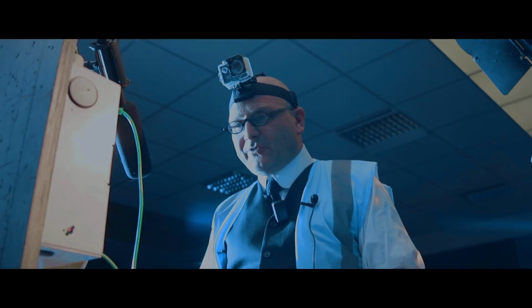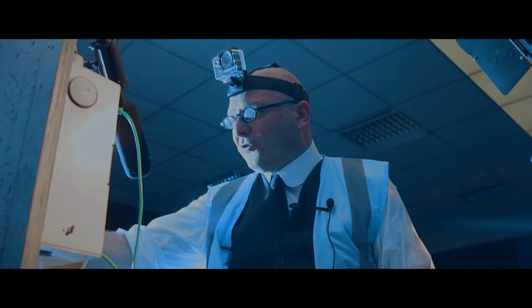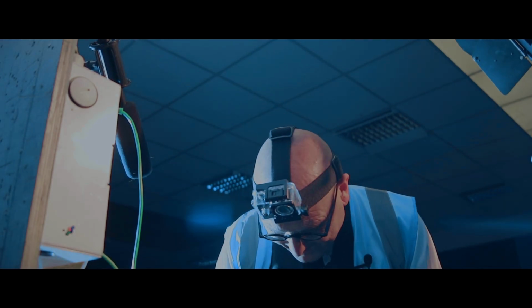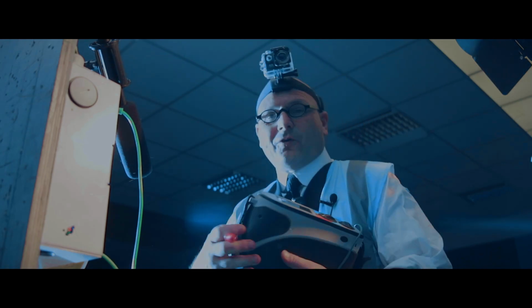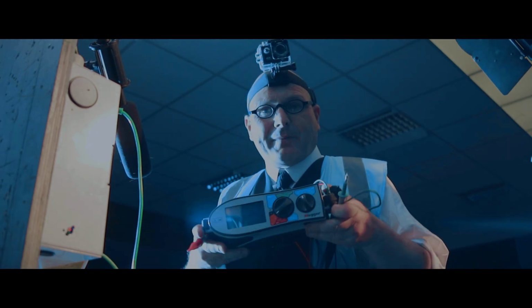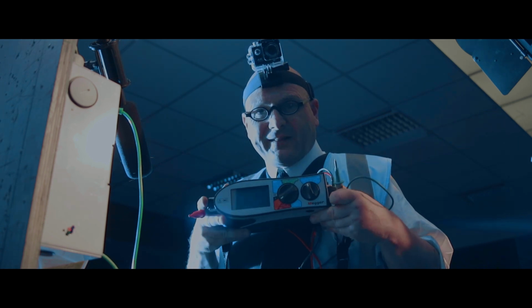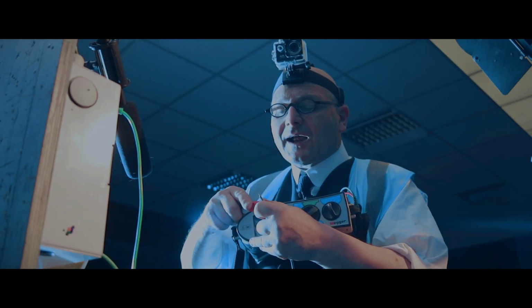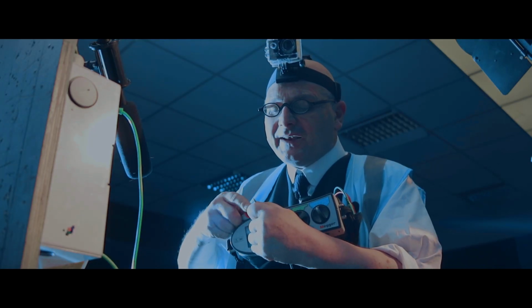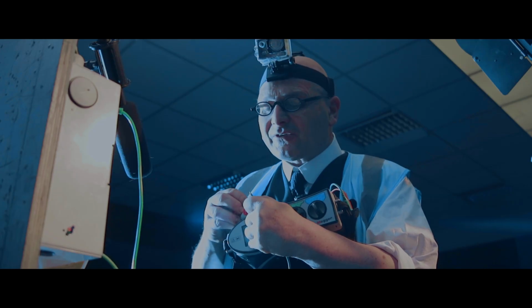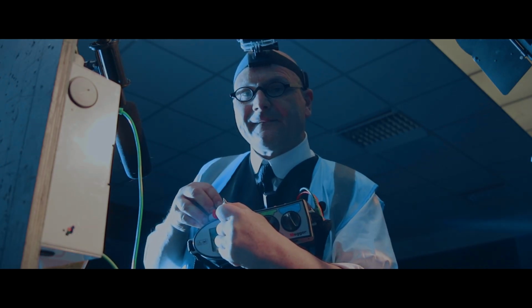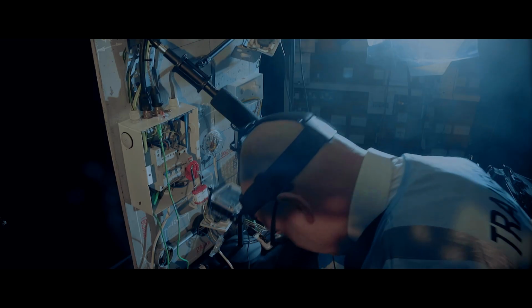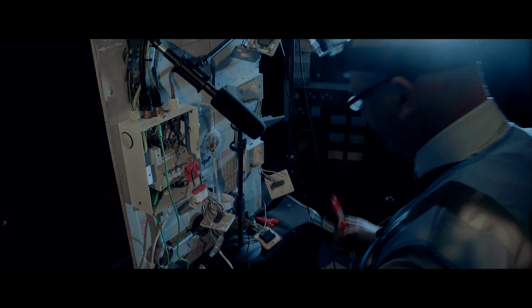In this instance, I'm going to be looking at my socket radial 2.5mm power circuit. Remember to put your MFT back to low resistance ohms, if it's not already there, and clamp these two tightly together with a tight electrical contact in order to null the leads. Let's see if we nulled. There we go, null the leads.